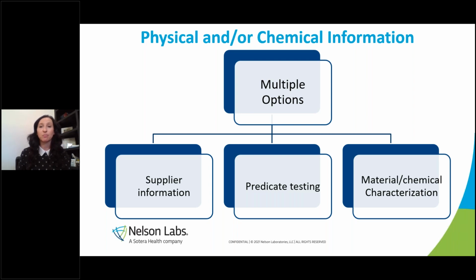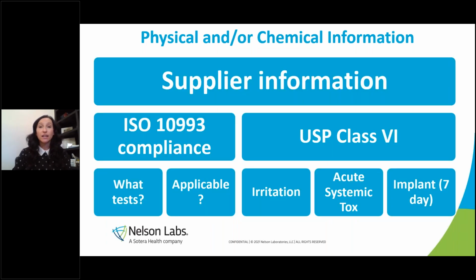So let's talk a minute about supplier information. I love to get information on products or materials that are already claimed to be biocompatible. A lot of times I'll see things like ISO 10993 compliance or USP Class 6. It does tend to make me ask more questions to the supplier, which I typically can get those answers for, so I know they're cooperating pretty well. When we say ISO 10993, I don't exactly know what that means because there are over 20 standards and multiple tests in each standard. So I like to ask for clarification on which standards were followed or which tests were performed.